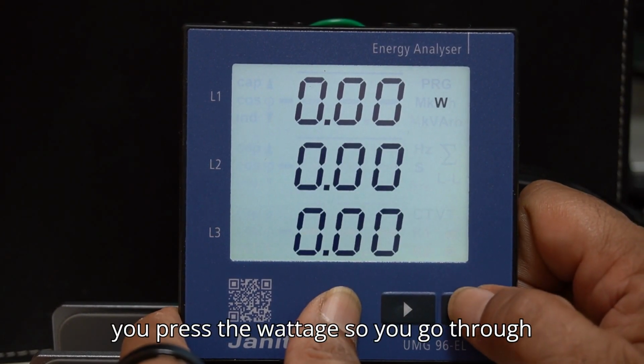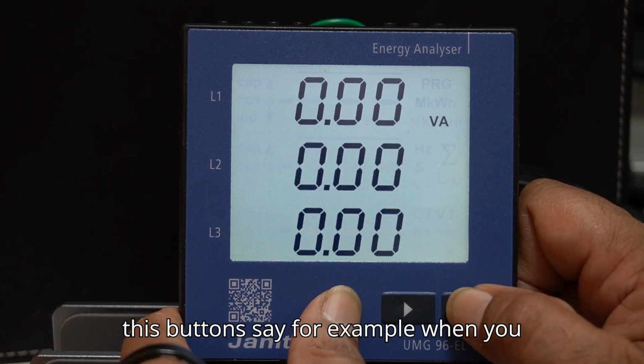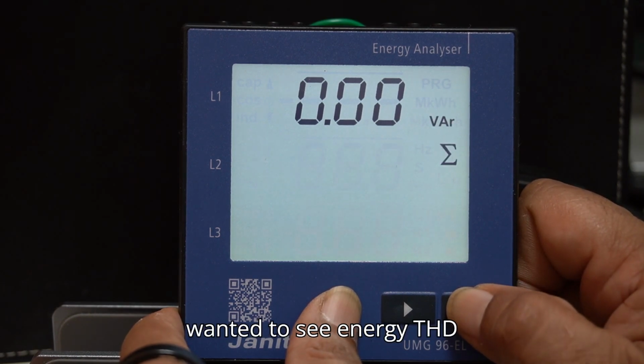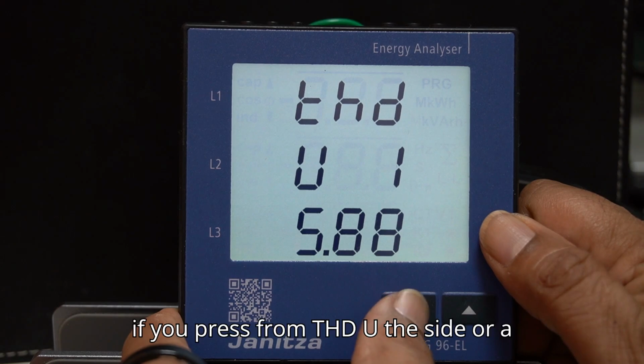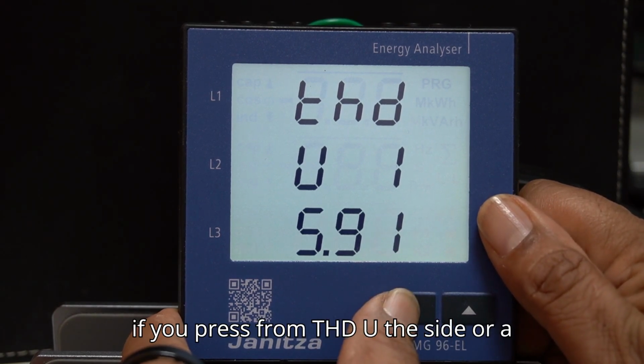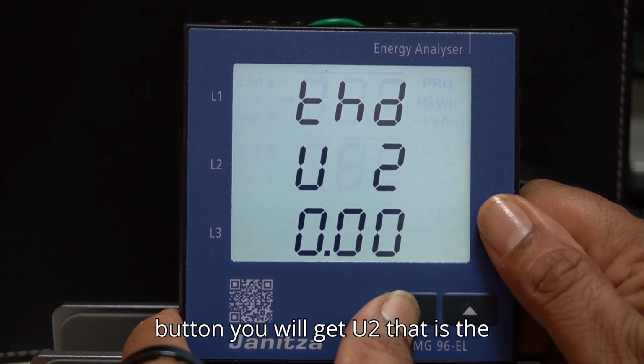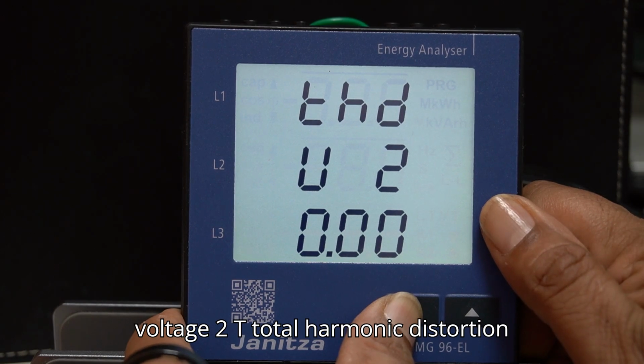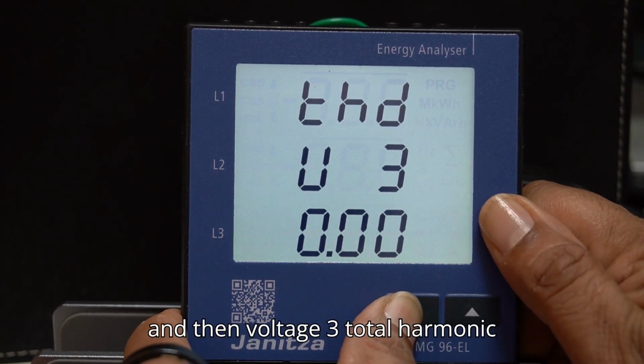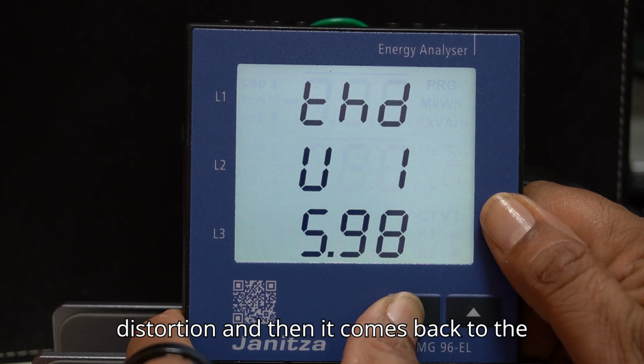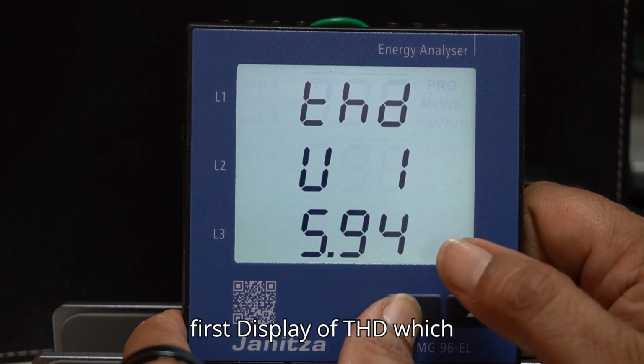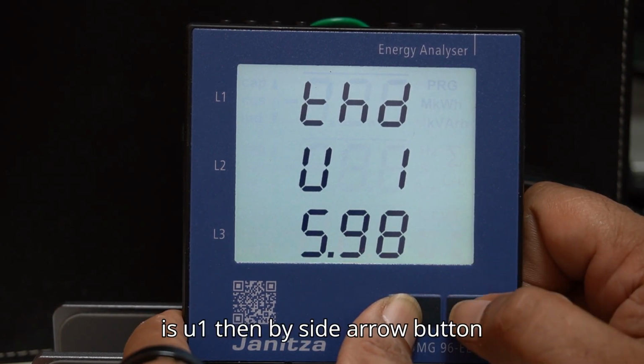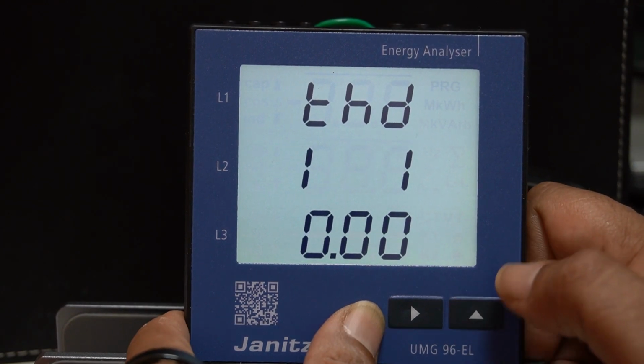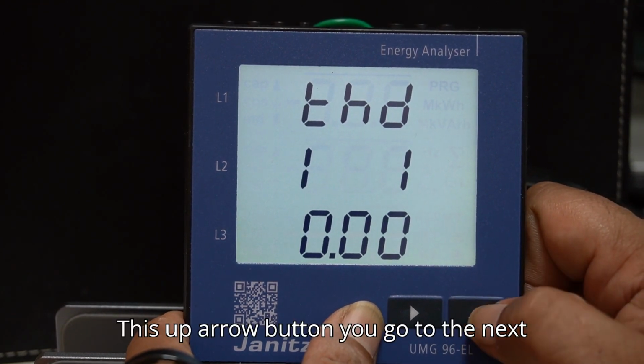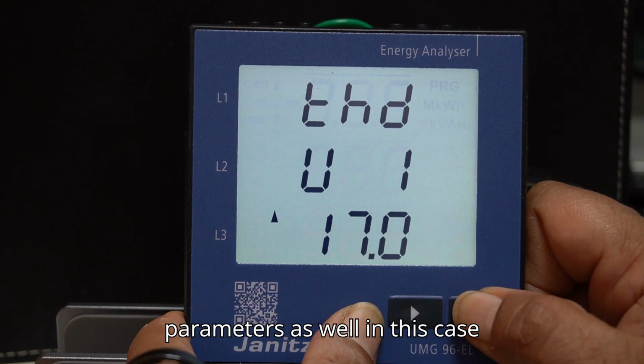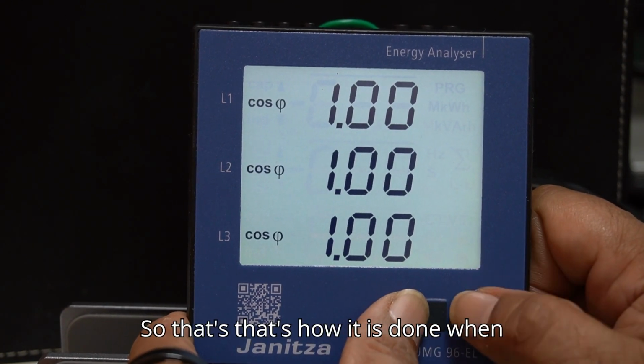Then again you press for the wattage. So you go through these buttons. For example, when you wanted to see THD, if you press the side arrow button from THD U1, you will get U2, that is the voltage 2 total harmonic distortion, and then voltage 3 total harmonic distortion, and then it comes back to the first display of THD, which is U1. Then by the up arrow button, you go to the next parameters as well. So that's how it is done.